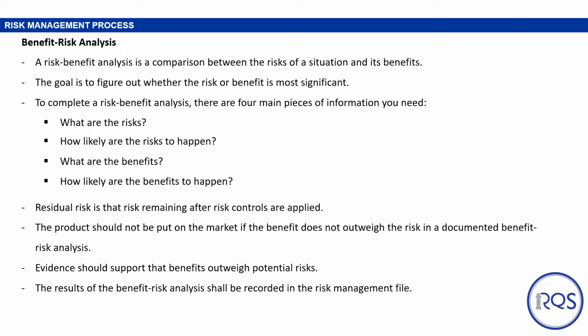As mentioned earlier, residual risk is the risk remaining after risk controls have been applied. The product should not be placed on the market if the benefit does not outweigh the risks, and there should be a documented risk-benefit analysis. Evidence should support that benefits outweigh potential risks.